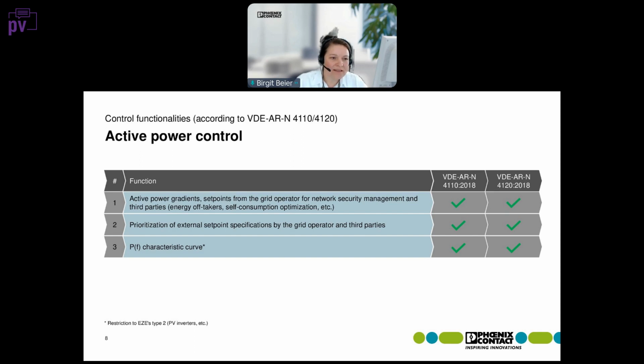So first, there are active power gradients, and you get set points from the grid operator for network security management and from third parties like energy off-takers or energy traders. The gradients are very important to get a smooth transition from one value to the next. Second, you have a prioritization of external set points between the grid operator and third parties. And then you have a characteristic curve, the active power as a function of the frequency.